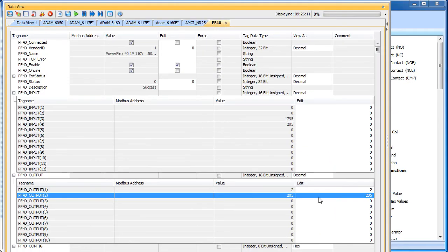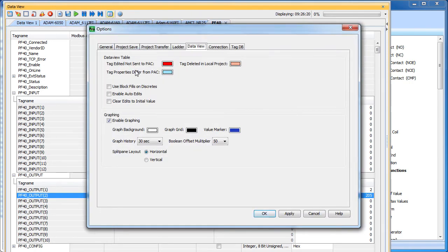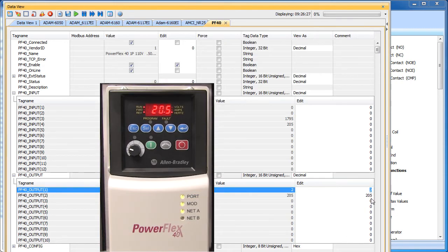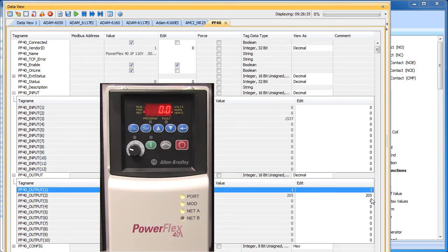Now it's a little bit of a pain to enter the data and then have to click this write button each time you want to do anything. So let me show you a little trick here. If you go up to Options, under the Data View tab, you can enable Auto Edits. Now if I want to stop the drive, I just put a 1 here and as soon as I hit return, that automatically gets written out and the drive ramps down to 0 Hz.